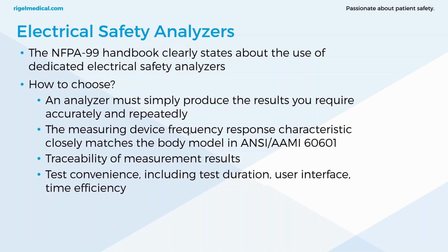So the first 3 points there, if you're picking from a reputable manufacturer of biomedical test equipment, then you only really need to worry about user preference. So test convenience, including test duration, user interface, time efficiency. It could be the support you get from the manufacturer. It's all, at the end of the day, ultimately user preference. So grab a demo from one of the manufacturers, from the representative, try it out, see what you think, and then that gives you an idea of which analyzer you prefer and want to implement in your organisation.